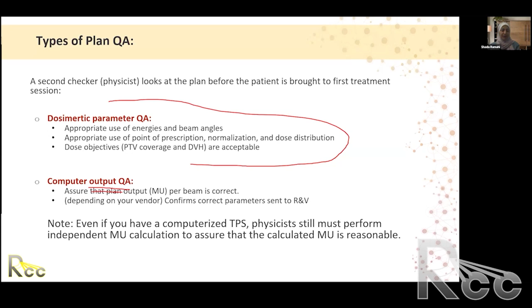After you verify the plan technicalities, now you want to go to the output. And depending on your vendor, I don't want to mention any names, some vendors require that you also export the plan to the record and verification system. So the second checker not only wants to verify that the monitor units are correct, but also that the plan has been exported properly, so the linear accelerator can execute that plan.